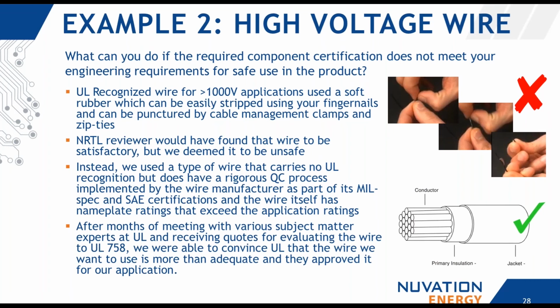So we're working with UL here on this specific problem, and it was actually a pretty straightforward process. It definitely had some challenges, where we were having to go around with various subject matters at UL about this. It took about 2 months to get to a point where the wire was approved, but we were receiving quotes saying that we had to take it through UL 758, which would have added 5 months to the schedule. And this is on a wire that really exceeds the actual requirements of UL 1973.